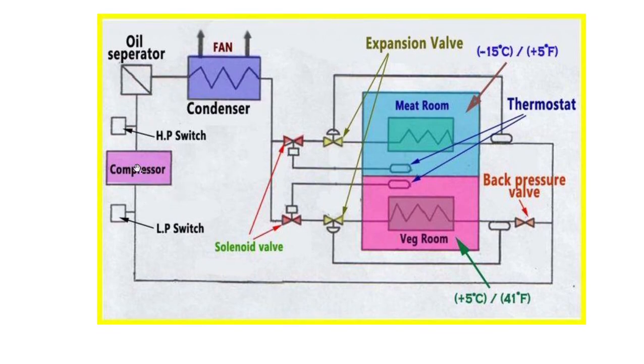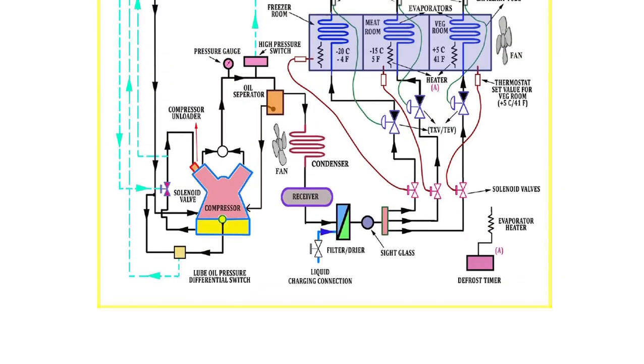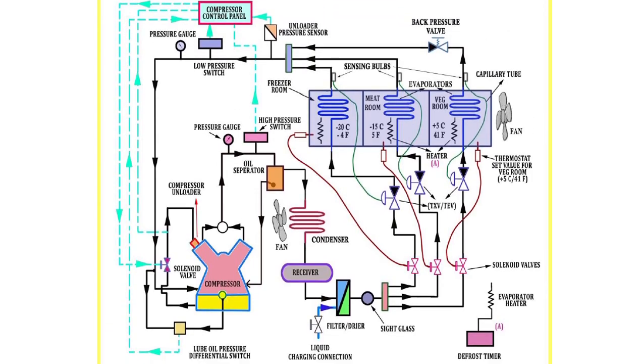Here is one more block diagram: compressor with LP and HP cutouts, oil separator, condenser with fans, and then the meat room and veg room each with expansion valves and solenoids. The sensing bulb controls the TXV. The back pressure valve is present only on the veg room side, not the meat room, because pressure is lower in the meat room and higher in the veg room due to the higher set temperature — plus 5 versus minus 15 degrees. This diagram is very important and surveyors may ask you to draw it. Thank you for your valuable time.